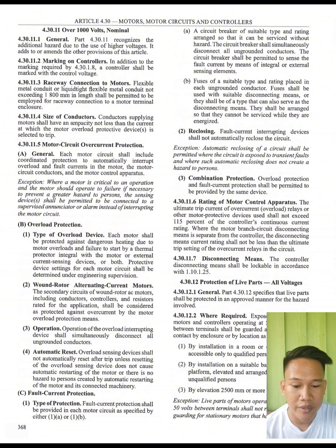Fourth, we have automatic reset. Overload sensing device shall not automatically reset after trip unless resetting of the overload sensing device does not cause automatic restarting of the motor, or there is no hazard to persons created by automatic restarting of the motor and its connected machinery. So C, fault current protection. First, type of protection. Fault current protection shall be provided in each motor circuit as specified by either 1A or 1B.